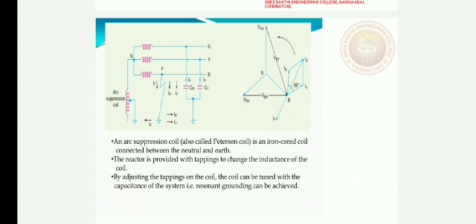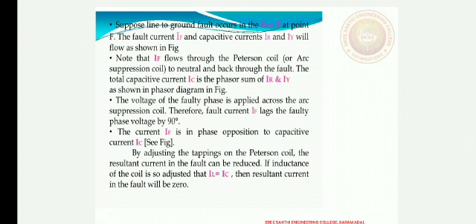An arc suppression coil is an iron core reactor similar to an oil immersed transformer connected between the neutral of the system and earth. This coil is provided with a number of tappings so that it can be tuned with a capacitance which may vary due to varying operating conditions. As the system operation is similar to an isolated neutral system, the phase to earth voltage of the healthy phase is root 3 times the normal phase voltage, and the resultant capacitive current is 3 times the normal charging current of one phase. The resultant capacitive current will lead by 90° the faulty phase voltage, while the fault current lags by 90° the faulty phase voltage.